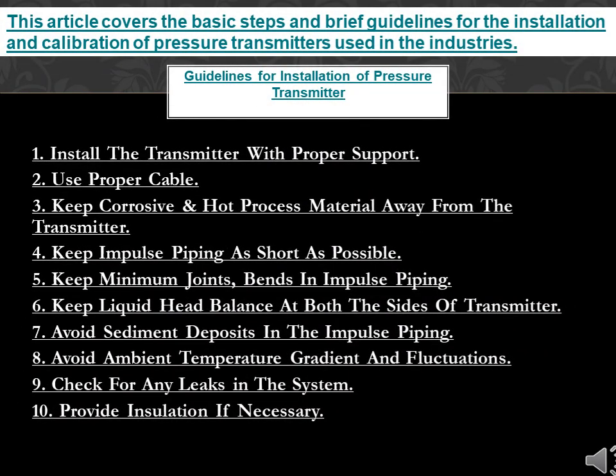This article covers the basic steps and brief guidelines for the installation and calibration of the pressure transmitters used in the industry. Guide for the installation of pressure transmitter. Install the transmitter with proper support. Use proper cable. Keep corrosive and hot process material away from the transmitter.